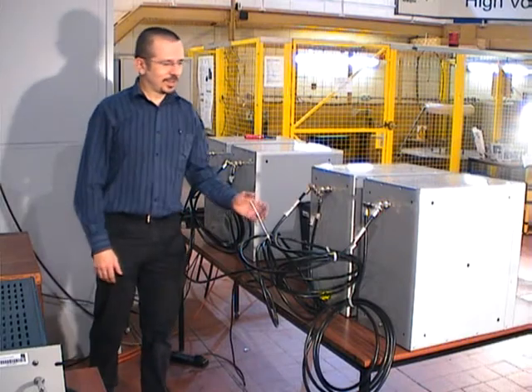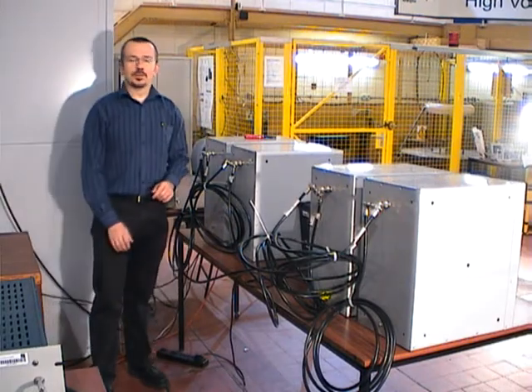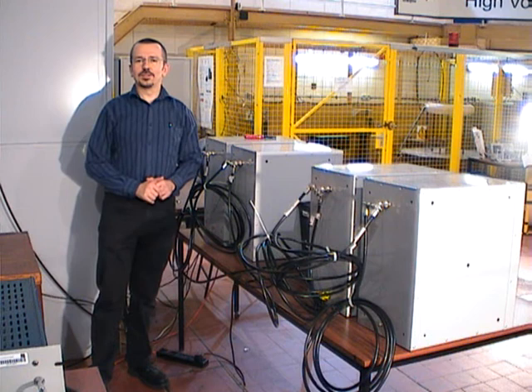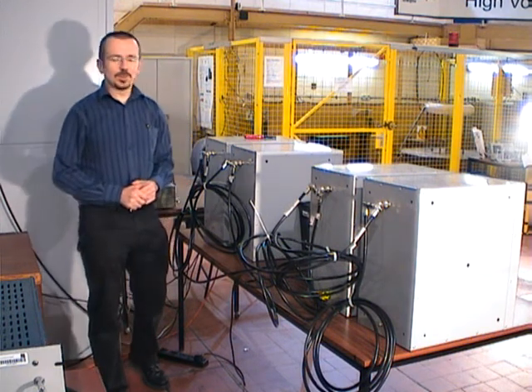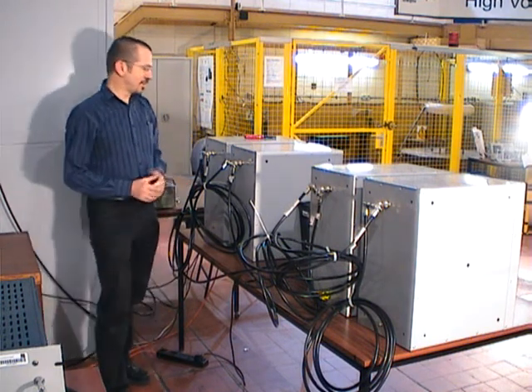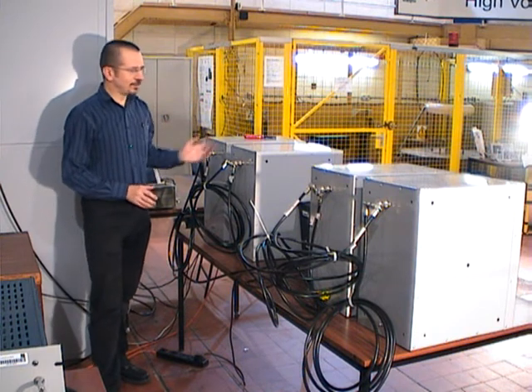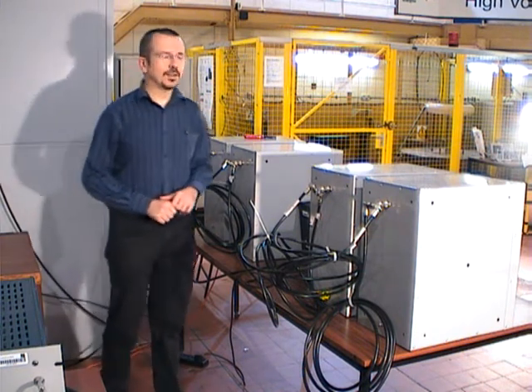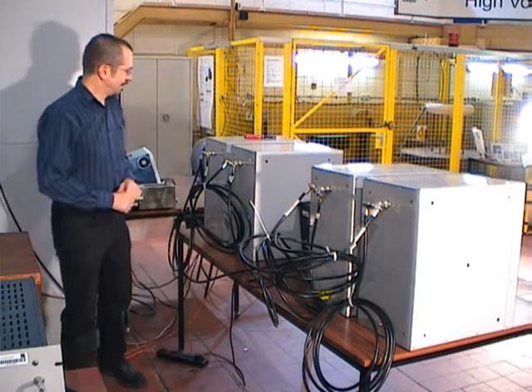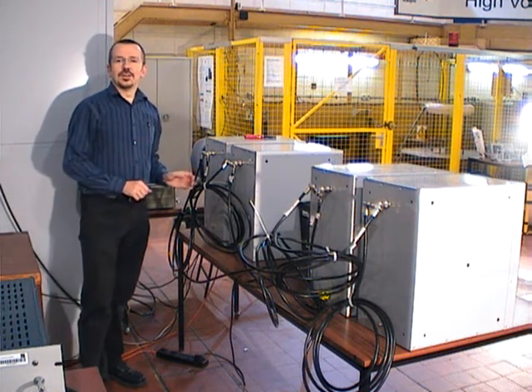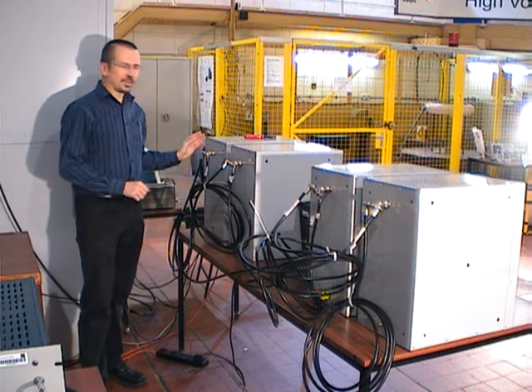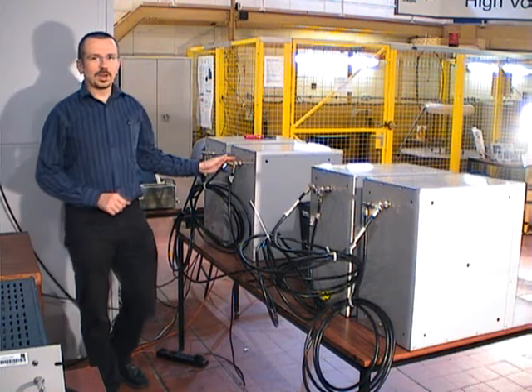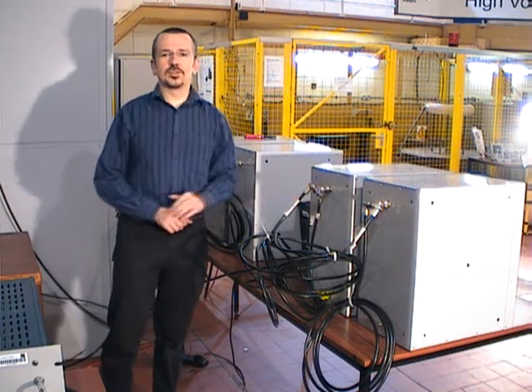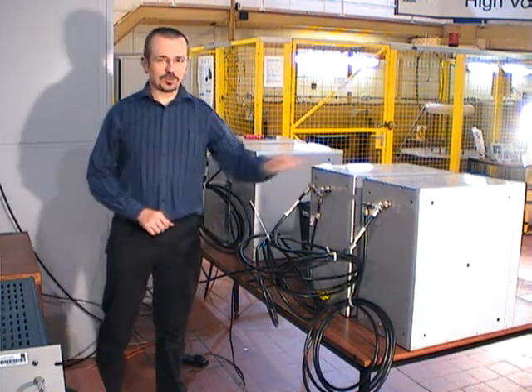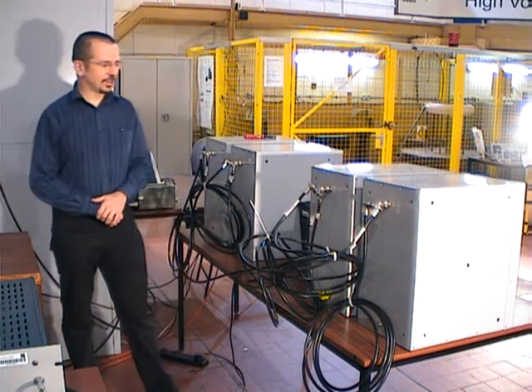The cable loop we can see at the back of the system can be made up to suit the separation of the individual items of plant that need to be monitored. These don't necessarily have to be all the same thing, although here we've just got boxes to represent items of switchgear. The cable loop consists of several different lengths of cable, and at each entry point where you require a partial discharge sensor, there's a T-piece with a small antenna inside that will detect the partial discharge.